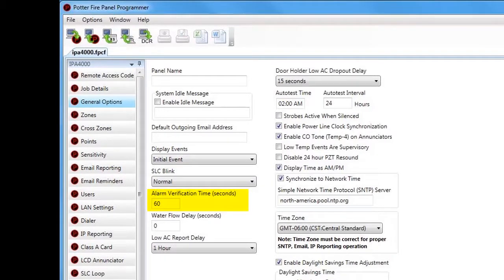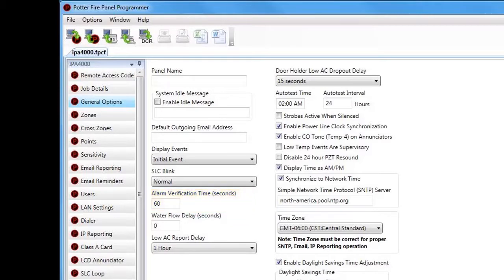The next option is Alarm Verification Time, set in seconds. This is where you set the alarm verification time for your smoke detector devices. Each individual smoke detector can be set up to activate under alarm verification. You can enter any number between 30 and 60 seconds. Each smoke detector can individually be set up for alarm verification — that designation is made under the Points section of the software.